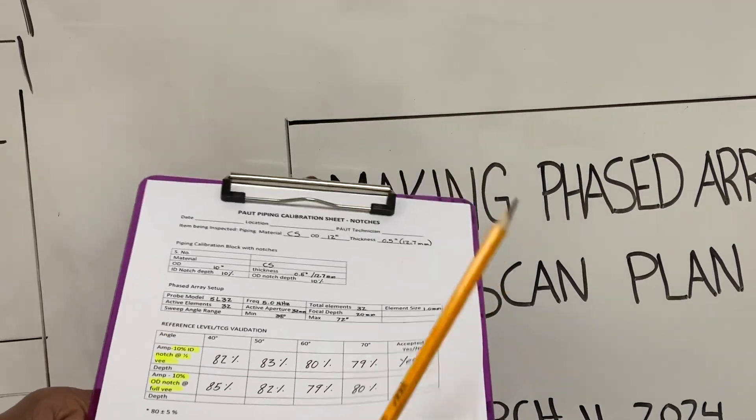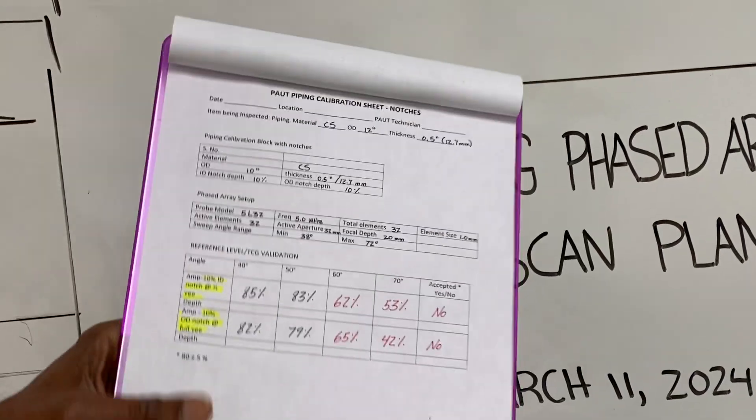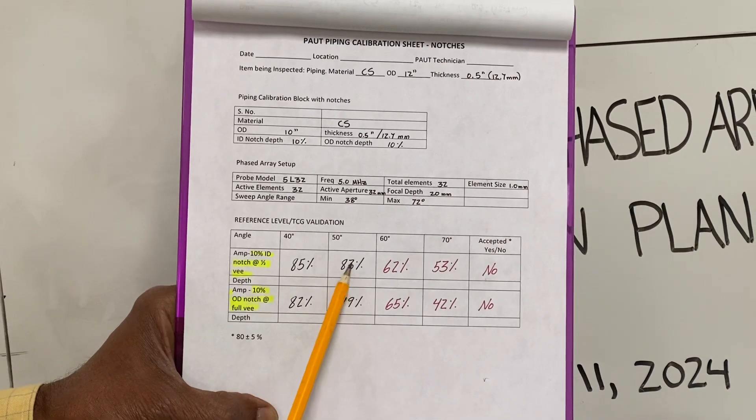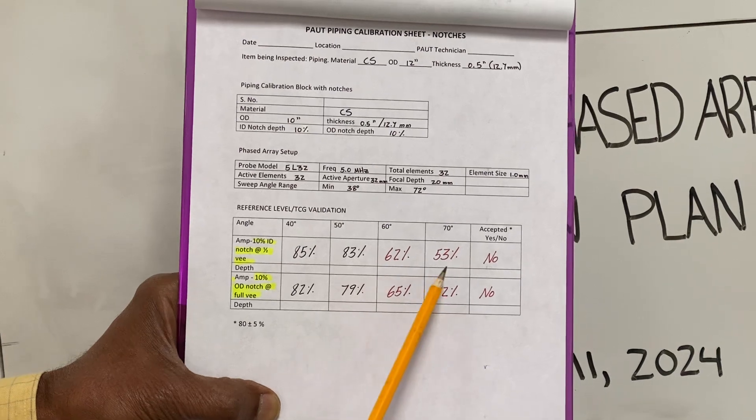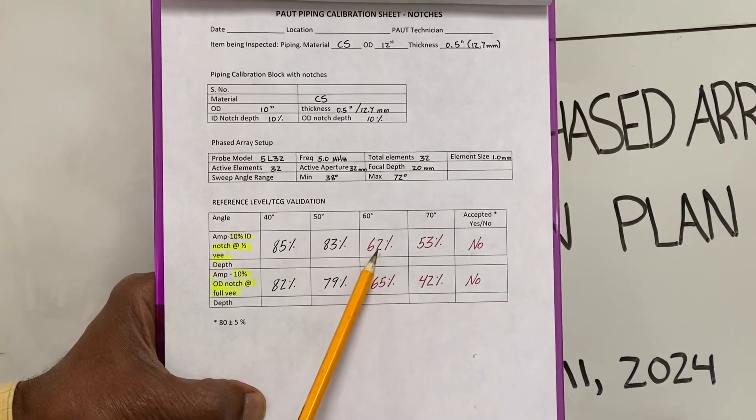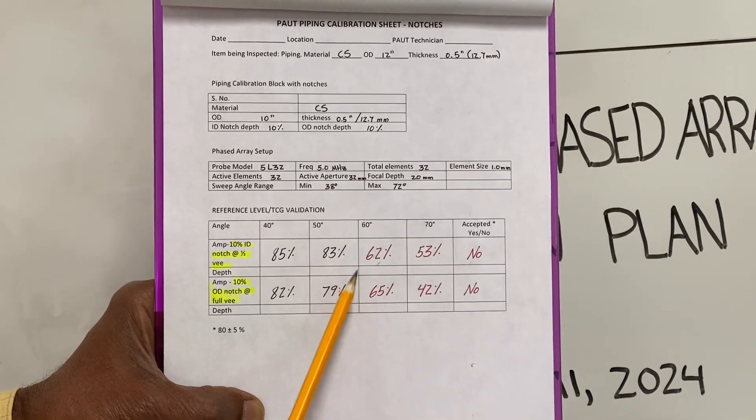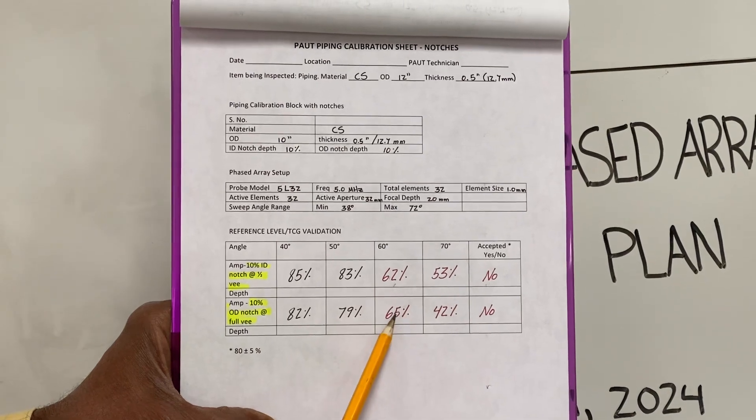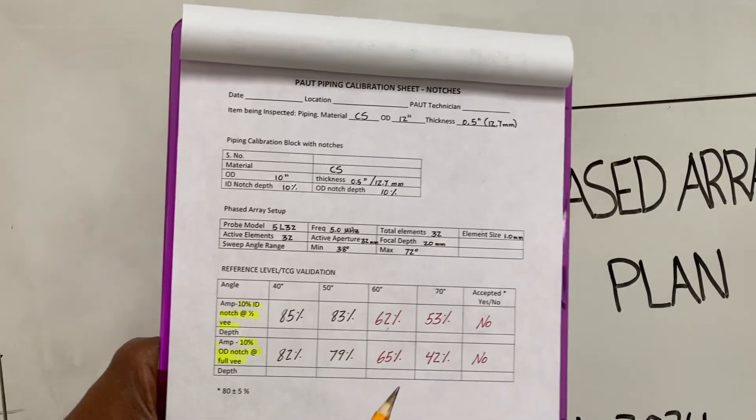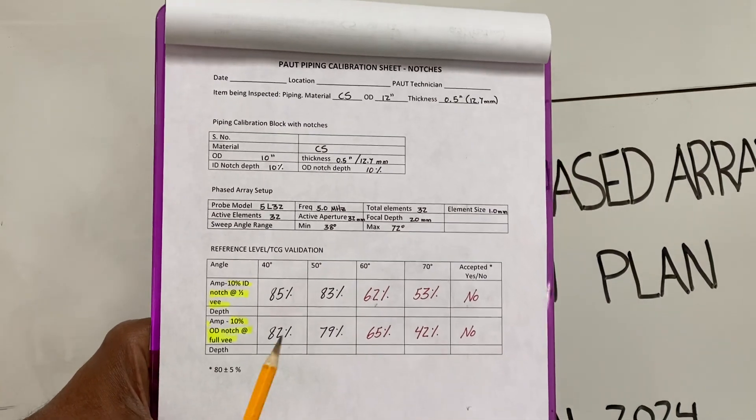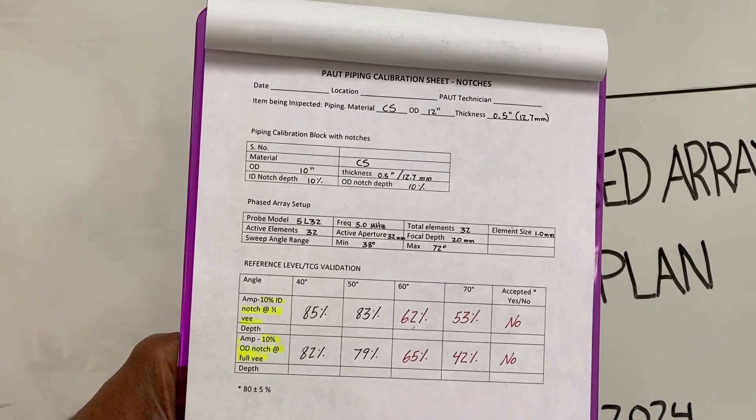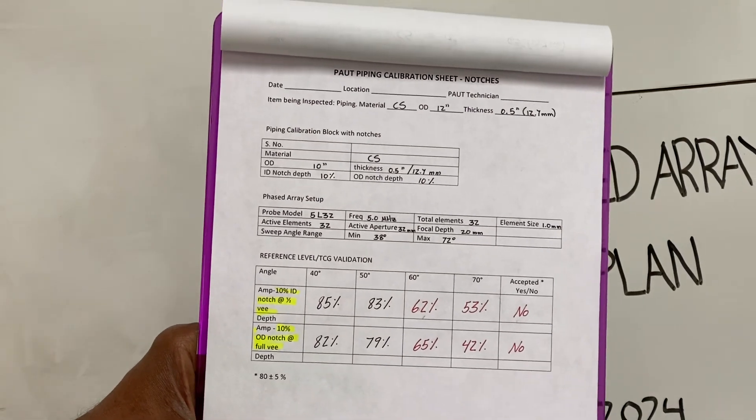Now what we have is an unacceptable calibration, which is shown here. In this case, we have at 40 and 50 it is acceptable, it's like 85% and 83%. However, at 60 degrees and at 70 degrees, we are getting amplitudes which are significantly lower than 80%. Here we have 62% and 53%. So if you get these kinds of numbers on the ID notch and the OD notch, then this calibration is not acceptable. So this is step number one, as far as the PAUT inspection is concerned, is to make sure that you have a valid calibration and your TCG is showing 80% for all the angles and for all the depths.